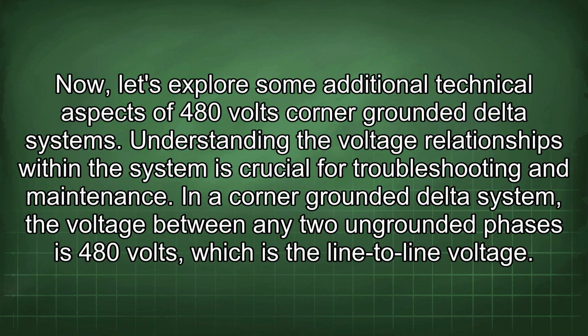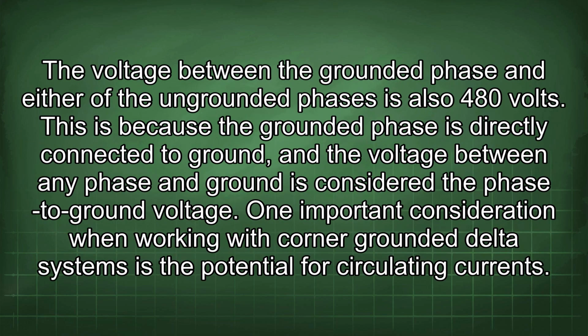Now, let's explore some additional technical aspects of 480 volts corner-grounded delta systems. Understanding the voltage relationships within the system is crucial for troubleshooting and maintenance. In a corner-grounded delta system, the voltage between any two ungrounded phases is 480 volts, which is the line-to-line voltage. The voltage between the grounded phase and either of the ungrounded phases is also 480 volts.